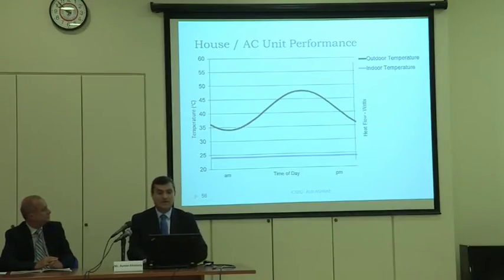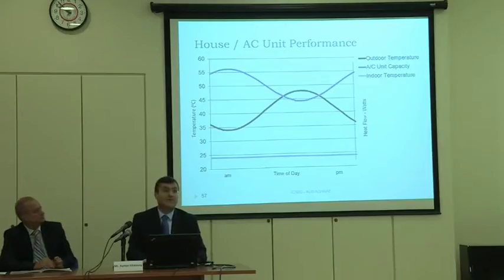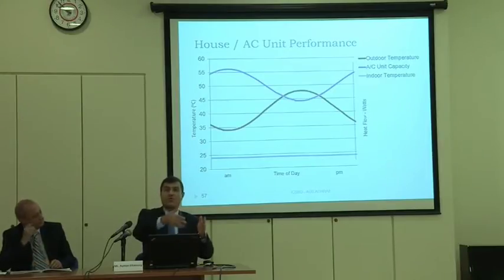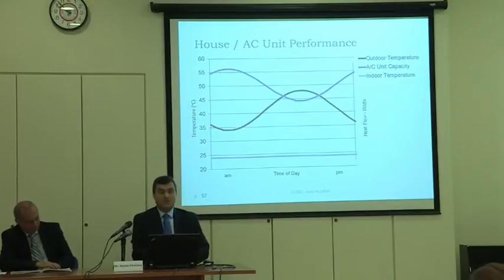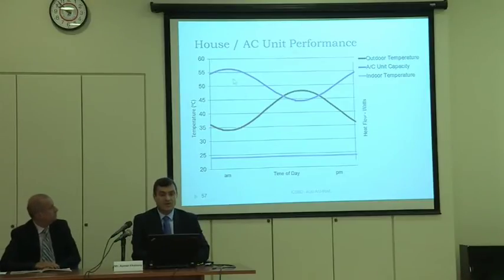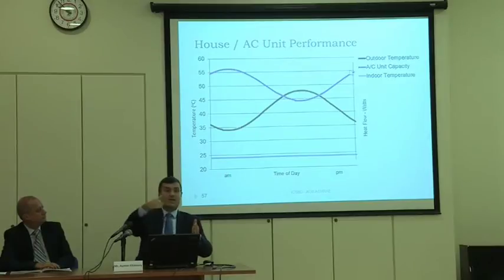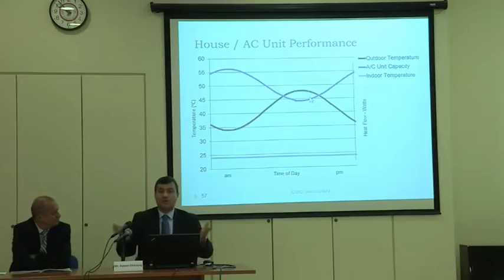This is the temperature outside. But if I put down the AC capacity, as we said earlier, the cooling capacity goes down with the temperature. So the cooling capacity used to give us this much at 35, but now it's going to give us a lot less, and this is a curve of the same machine during the day, the cooling capacity of the machine. So looking at this, you could see in this time in here, I will not have cooling. That means we need to raise the cooling of the machines.